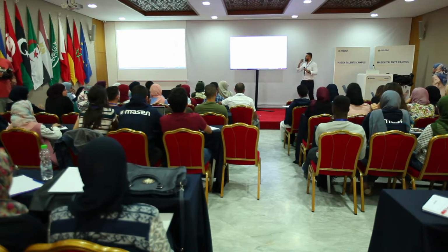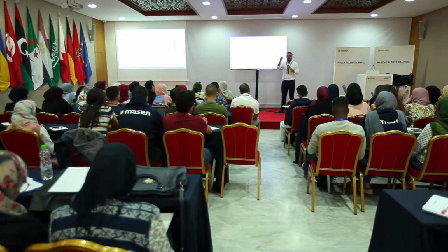Because you want to operate during the times of sun, but you also want to store. So you need to collect way more than what you would need at the nominal design point. We usually design for solar noon to operate at nominal point, at 100 megawatt, 120 megawatt. So you need to oversize that part, the number of heliostats in the tower and so on, and that ratio is what we call the solar multiple. Someone before asked about the solar multiple.